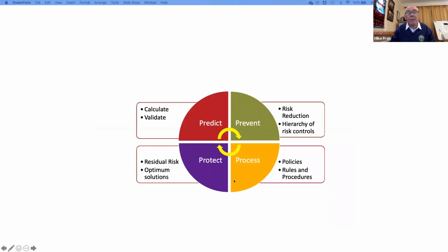And here we go with my 4 Ps approach to risk control for arc flash. It appeared years ago, actually, and I've modified it a few times since then, but I think I've got it about right now, so I'll stick to this one. We've got 4 segments, starting with predict in red, which is about calculating or validating the level of incident energy that we can expect. Prevent is about using the risk control measures and the hierarchy of risk controls that I'll speak about later. Process is about policy, rules, procedures, and so on, before we go into the protect segment, which is all about residual risk and optimum solutions.